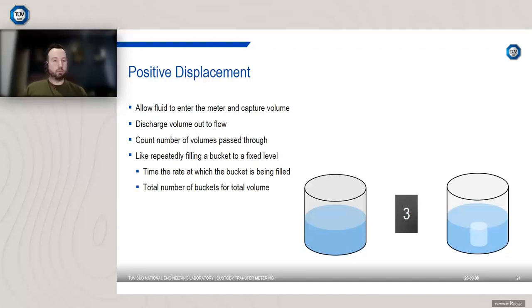So the next traditional technology is positive displacement. And how do these work? Well, they allow fluid to enter the meter, and they capture a fixed volume of that fluid. Once they've captured that volume, they then discharge that volume out to the flow. So it's quite simply count the number of volumes that pass through the meter, that gives you the total volume. So it's like repeatedly filling a bucket to a fixed level. You time the rate at which the bucket's being filled. Total number of buckets gives you the total volume.